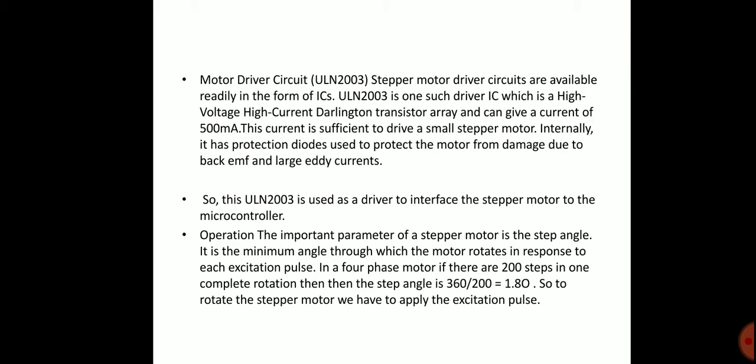An important parameter of a stepper motor is the step angle. It is the minimum angle through which the motor rotates in response to each excitation pulse in a 4-phase motor. If there are 200 steps in one complete rotation, then the step angle is 360 divided by 200, which is equal to 1.8 degrees. That is, to rotate the stepper motor we have to apply the excitation pulses.